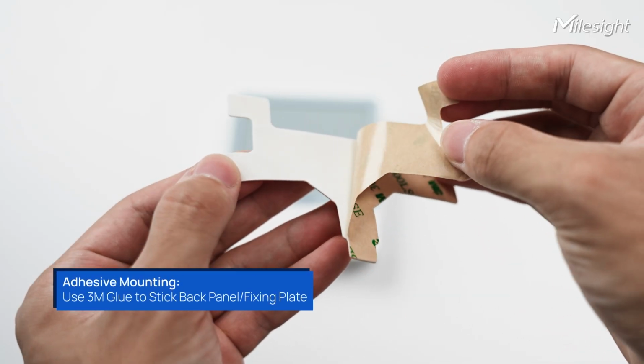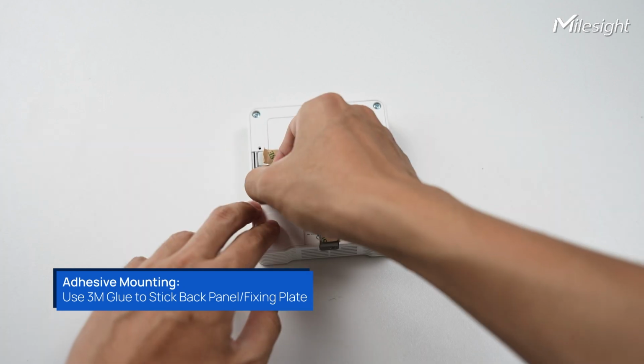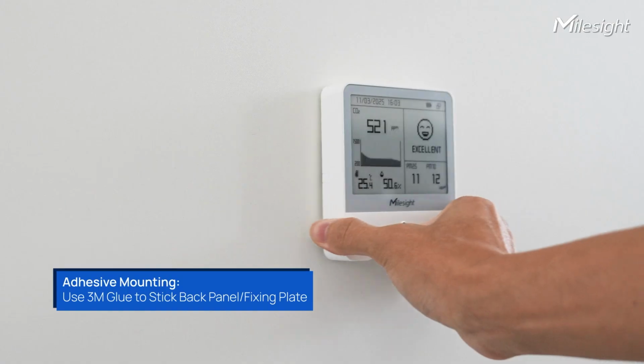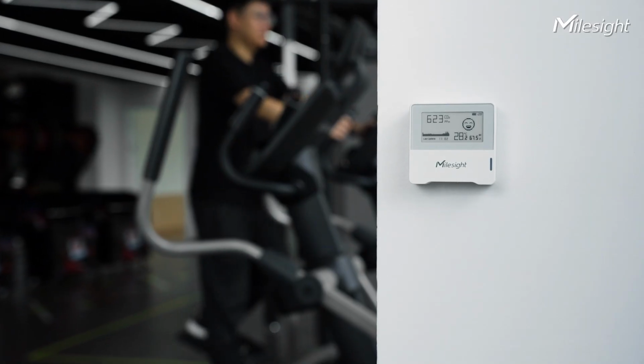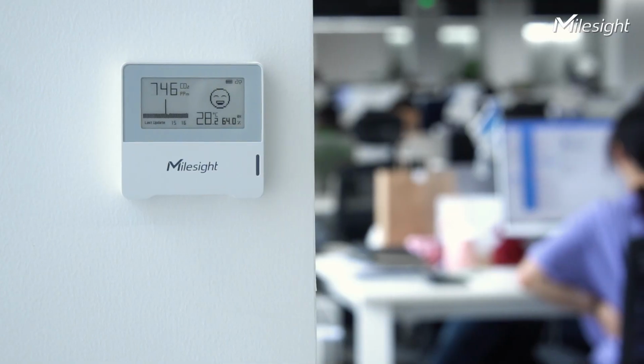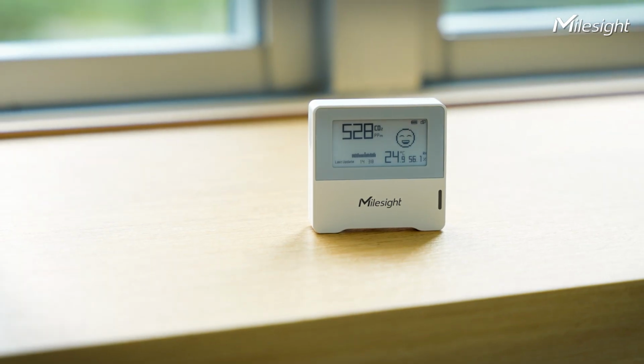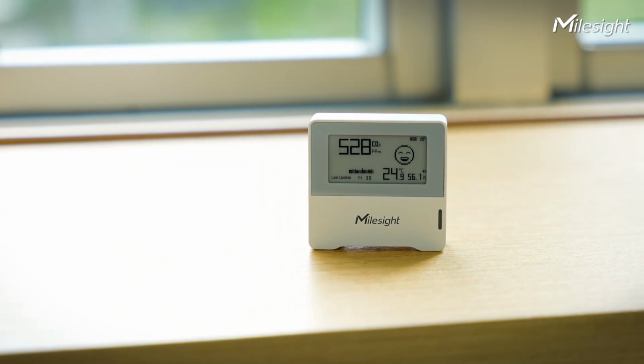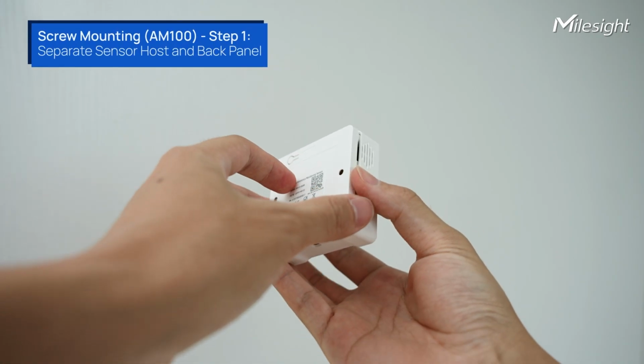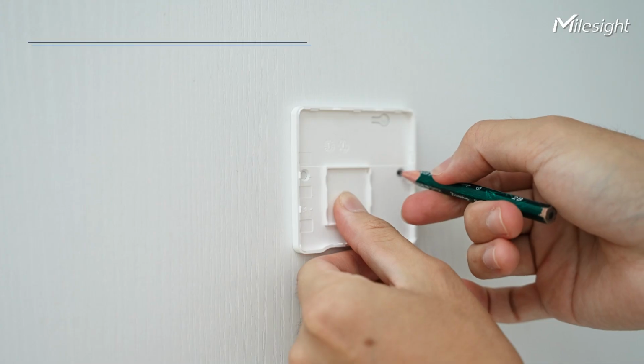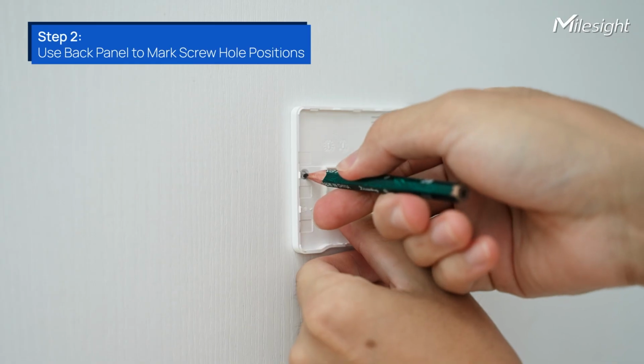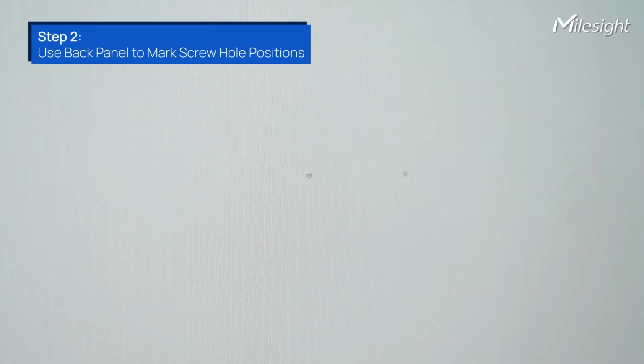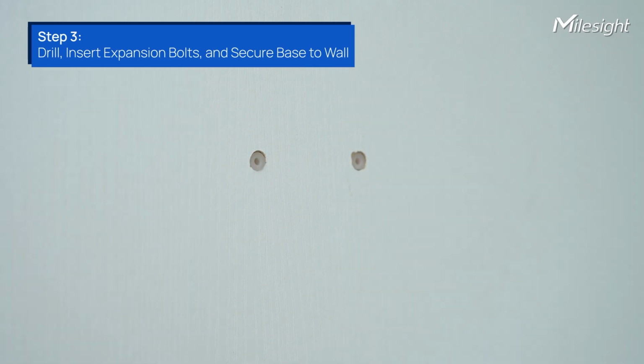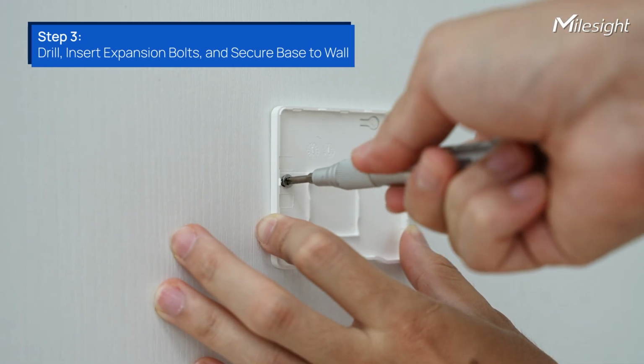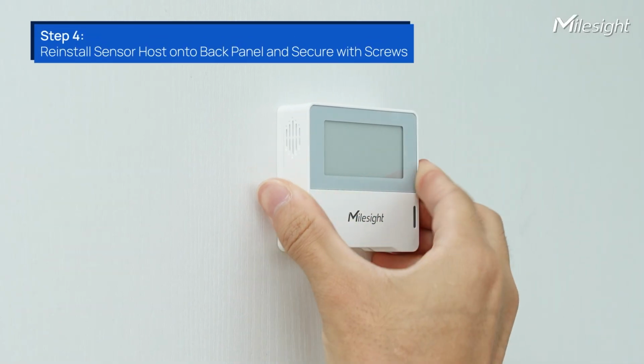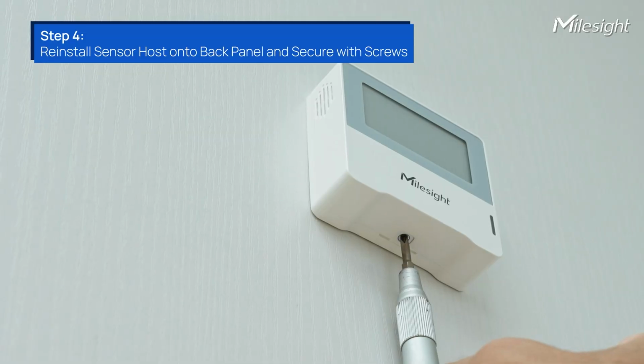First method, adhesive mounting. Simply attach the back panel or fixing plate using 3M adhesive. Then, install the device onto the plate. If you require a more robust fixation, or for specific device models, we recommend screw mounting. For the AM100 series, installation for this model involves 4 steps. Step 1. Separate the sensor host from the back panel. Step 2. Fix the back panel to the selected wall position and mark the screw hole locations with a pencil. Step 3. After drilling, insert the expansion bolts and use screws to firmly fix the base to the wall. Step 4. Align the sensor host with the back panel for installation and secure it with fixing screws.